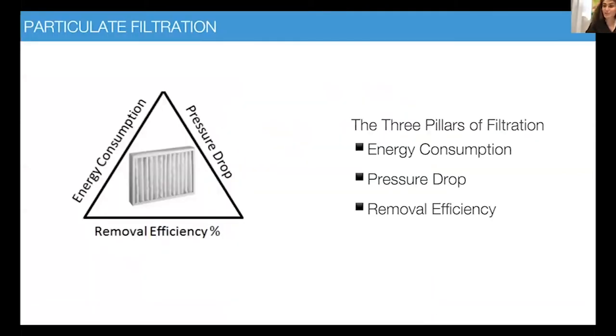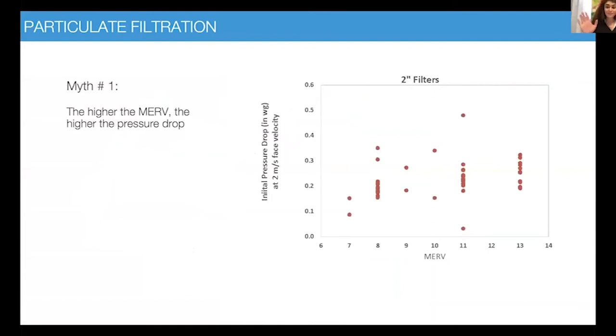So how to choose particulate filtration? There are also a lot of myths about how to choose a particulate filter. Typically, there's the first cost of the filter, the energy consumption, the pressure drop, and the actual efficiency. The first good news, as I mentioned, and I'm going to mention again, is that it's very easy to ask your distributor or your manufacturer for this ASHRAE test that tells you the pressure drop and efficiency. So it's not a black box. It's something that we have had access to for a long time. We have it in our buildings and it actually works very well.